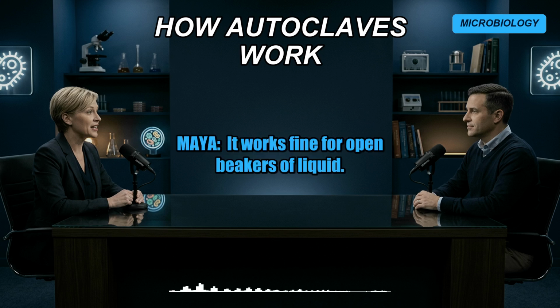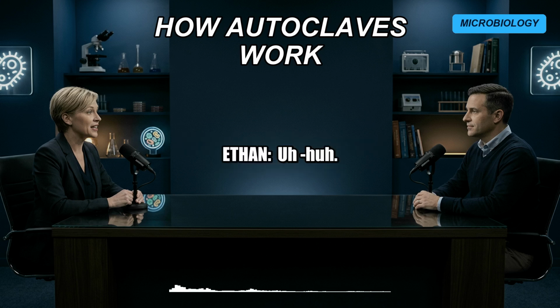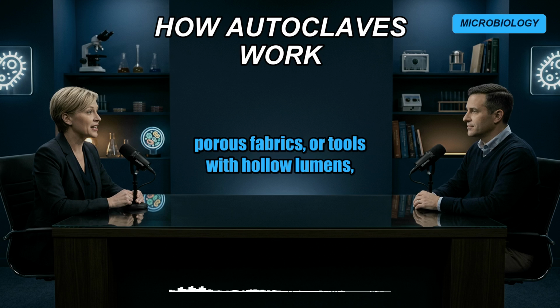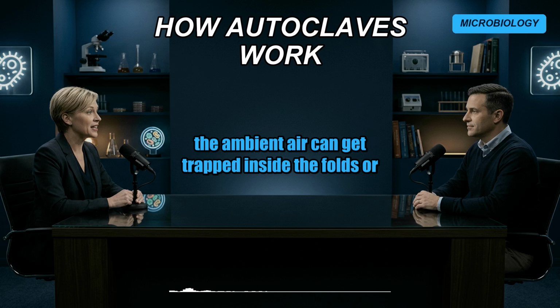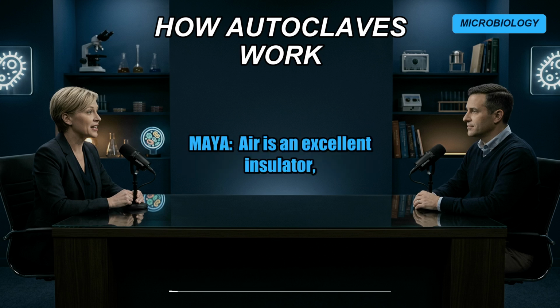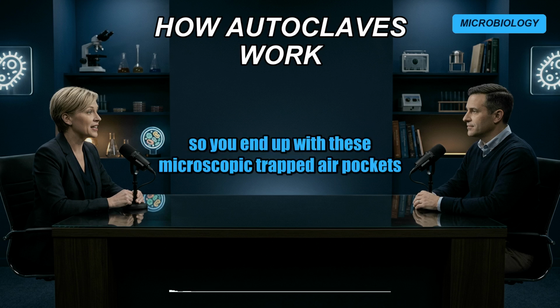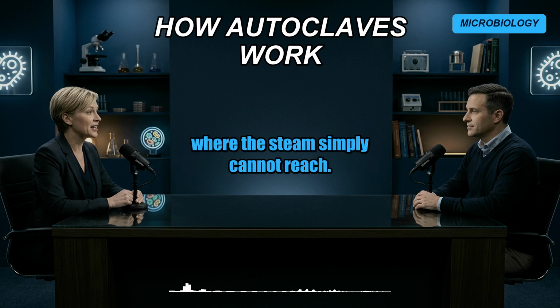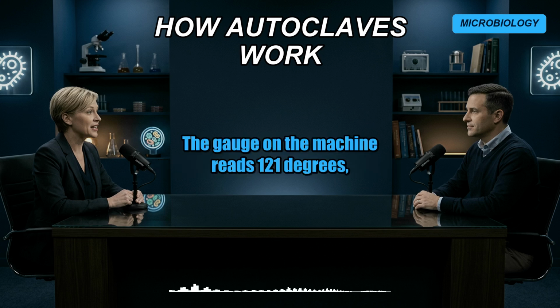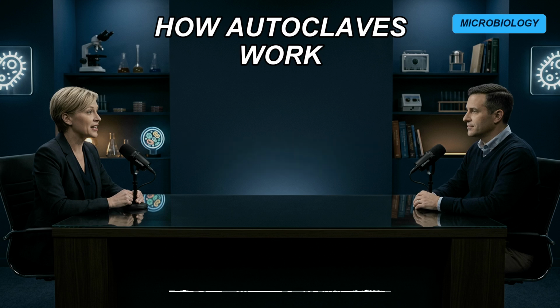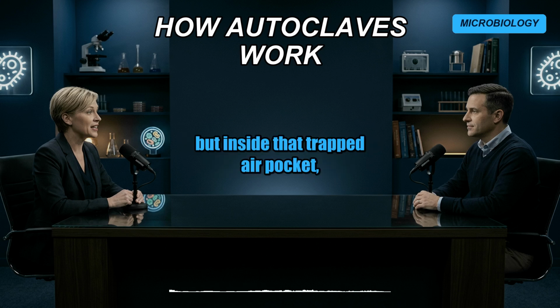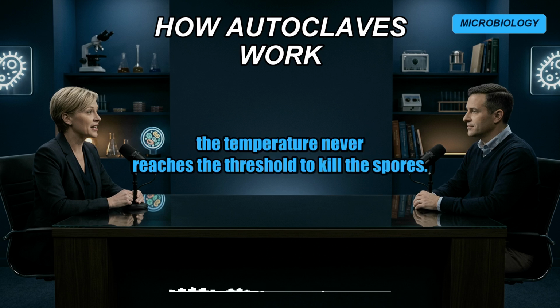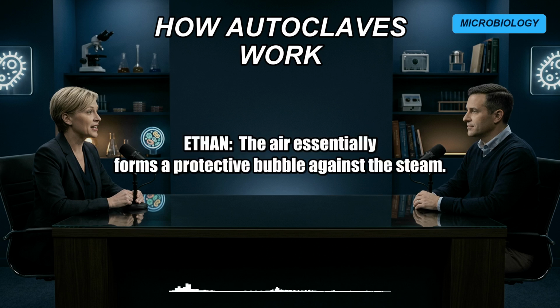Seems pretty straightforward. It works fine for open beakers of liquid, but if you have tightly wrapped surgical instruments, porous fabrics, or tools with hollow lumens, like a catheter tube, the ambient air can get trapped inside the folds or the tubing. Oh, I see. Air is an excellent insulator, so you end up with these microscopic trapped air pockets where the steam simply cannot reach. The gauge on the machine reads 121 degrees, the tape turns black, but inside that trapped air pocket, the temperature never reaches the threshold to kill the spores. The air essentially forms a protective bubble against the steam.